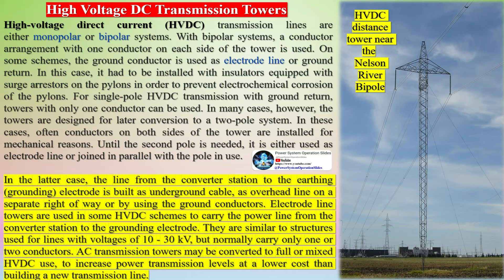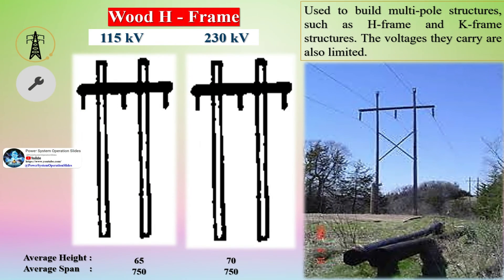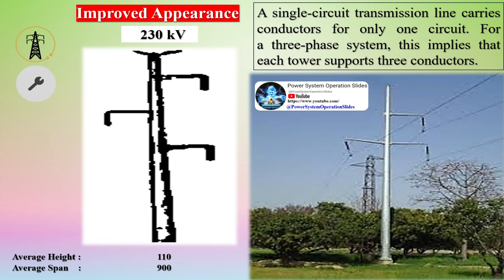HVDC transmission lines are either monopolar or bipolar systems. With bipolar systems, a conductor arrangement with one conductor on each side of the tower is used. On some schemes, the ground conductor is used as an electrode line or ground return, requiring insulators equipped with surge arresters on the pylons to prevent electrochemical corrosion. For single-pole HVDC transmission with ground return, towers with only one conductor can be used. The line from the converter station to the earthing electrode may be built as underground cable, overhead line on a separate right-of-way, or using the ground conductors.